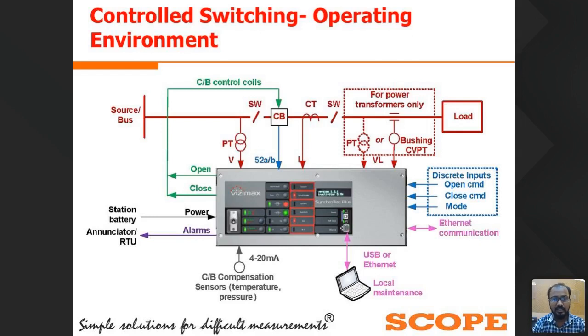We can differentiate the switching of any equipment into two types. One is the protection operation and the other is the manual operation. Whenever any fault occurs in the system, the protection relay will operate and execute the command to the circuit breaker. At the time of installing the control switching device, we are not disturbing the protection circuit, because at the time of any fault, the isolation of the healthy circuit from the faulty circuit is very important.